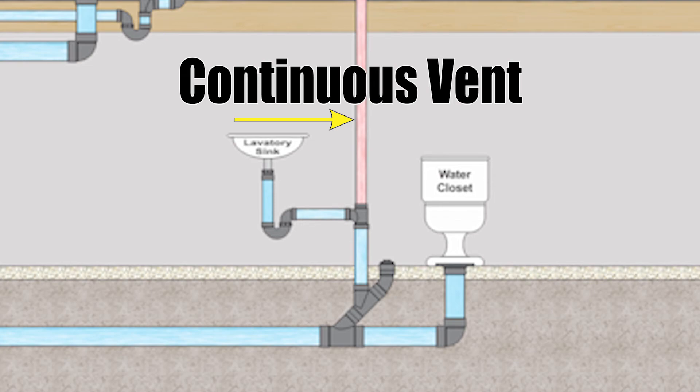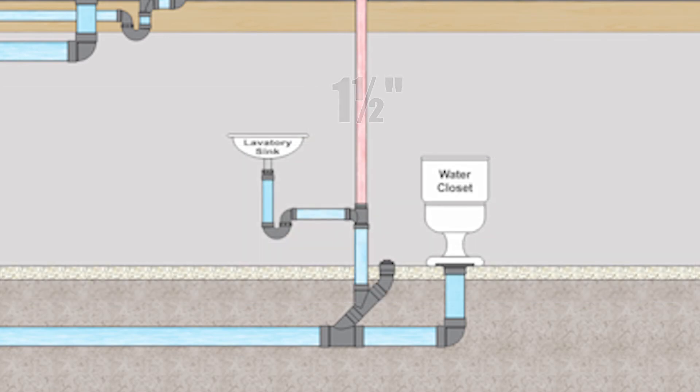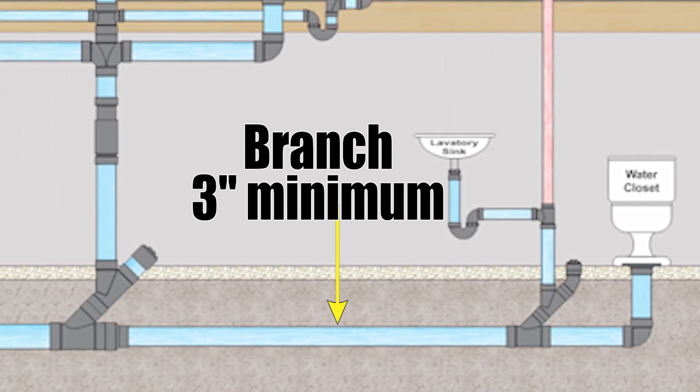But we can go and look at that vent pipe coming off the top of it. That is a continuous vent. If we use table 2.5.7.1 based on size of largest traps serve we would look at that water closet. That has a three inch trap. Therefore that continuous vent needs to be minimum one and a half inches. And when we continue downstream of this Y we have a branch and that branch will need to be three inches because we're serving a water closet which is three inches.